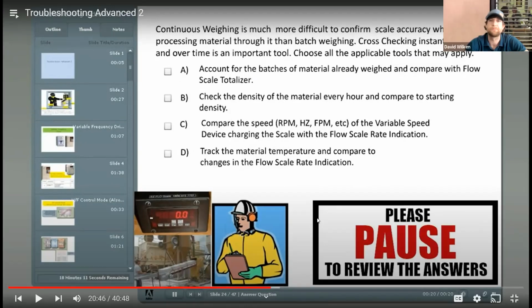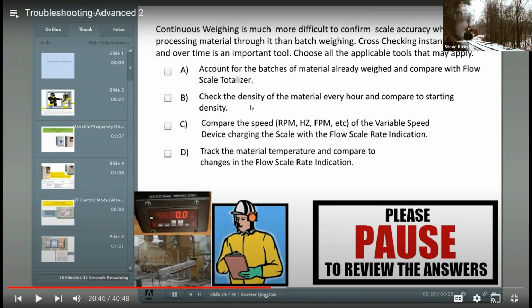What do you think, Nathan? You think A would be a good one to compare, to confirm your accuracy? I think A, B, and C. I don't know that we need to check the density every hour. I'm not sure that's a feasible one. That might work if you're on just dust, where you're counting on a volumetric measure against a rotary input. Likewise, the temperature might be important if you're dealing with asphalt. It should be corrected automatically, but is it being?